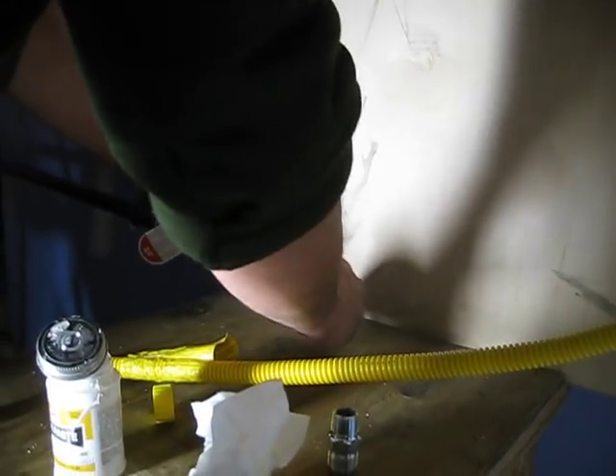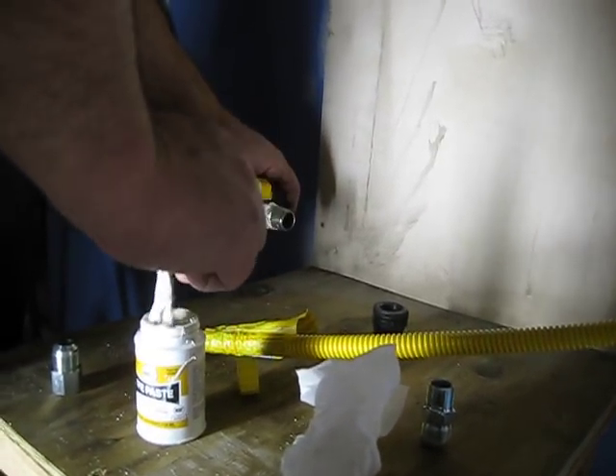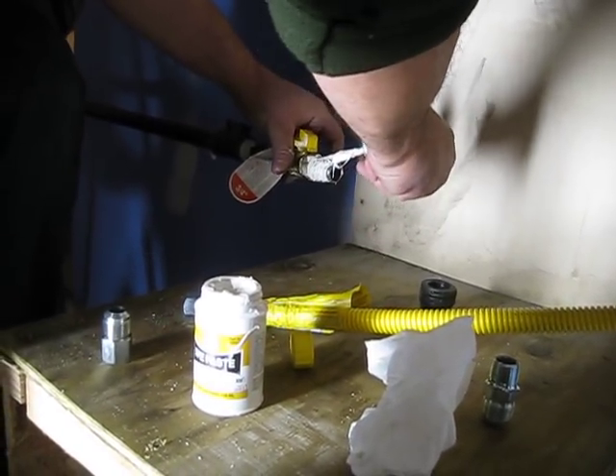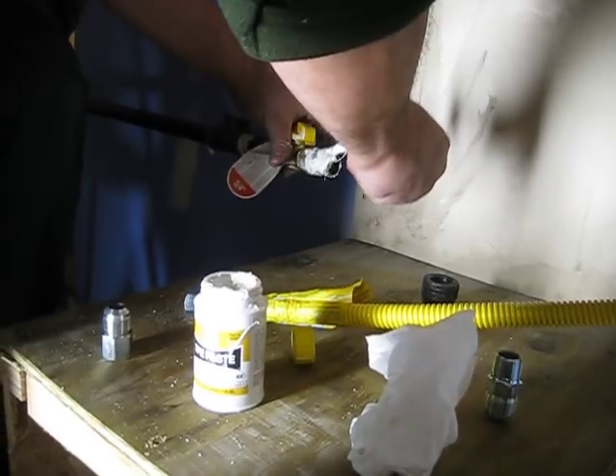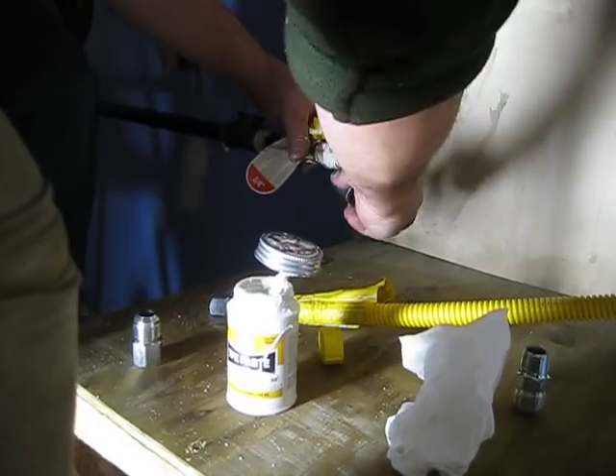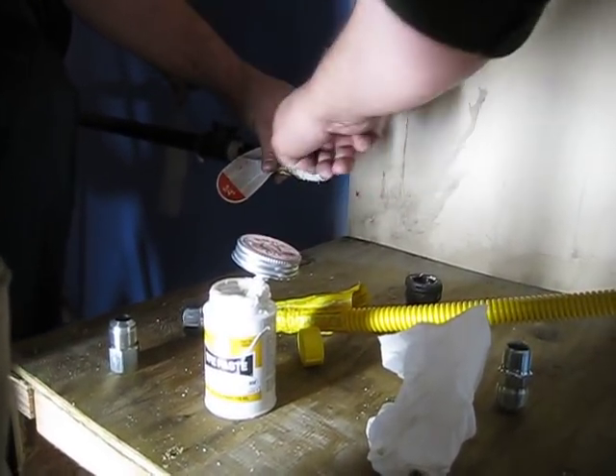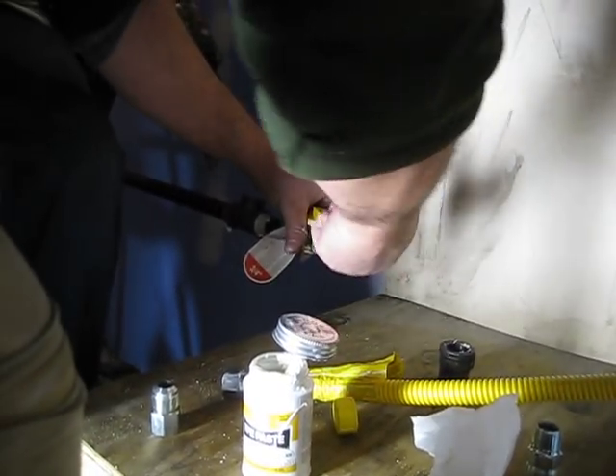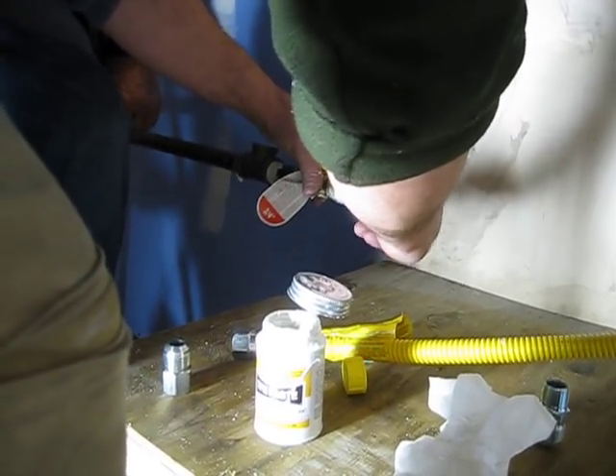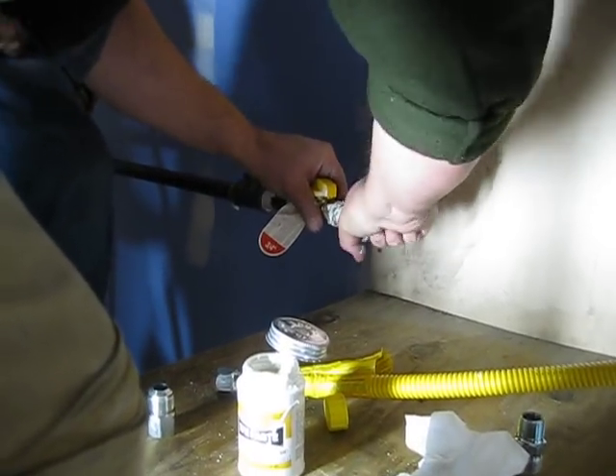Now, you know, you could always have a valve right here that turns both of them off. But I think it's better to have two valves. All right, now there'll probably be a valve outside to turn the propane tank off, if you know what I mean. Oh, right, yeah, the propane. Now, it's going to be hot to here all the time, and then it's going to be hot to here all the time. So my suggestion would be to have another one of these yellow valves right here. Just have everything in your mechanical room. And then when you pull your stove out to clean it, you'll have one of these 36-inch hoses. It's flexible. It'll pull out. You just got to be careful when you pull it out.